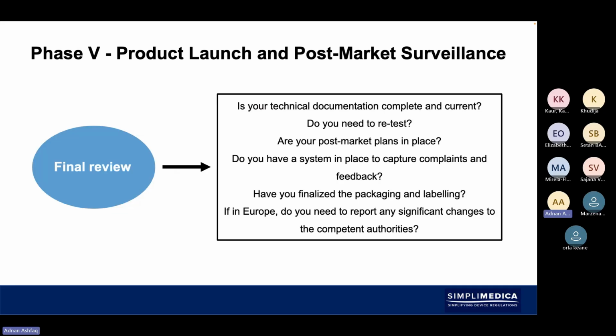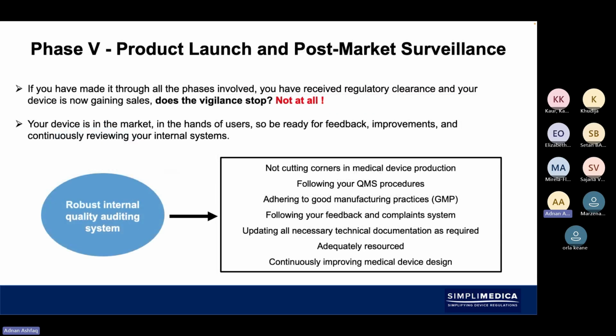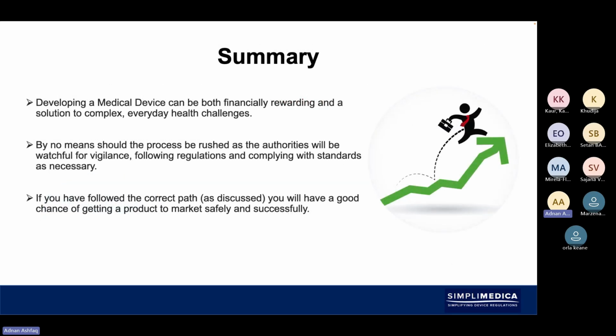And then you also need to look at whether you have any significant changes. In Europe, you have to report those significant changes to the competent authorities and inform them that you've made a change to your device. And then the technical documentation might also need to be changed. Think about vigilance. Always make sure that you've got a robust system in place that can handle anything for post-market and recalls. Don't cut any corners, follow your QMS procedures, adhere to good manufacturing practice, follow your feedback and complaint system, and always update your technical documentation as required. Make sure that you're adequately resourced, and then continue to improve your medical device design.